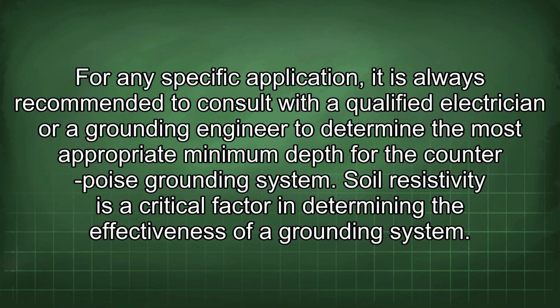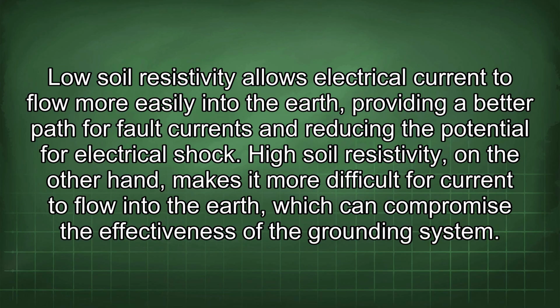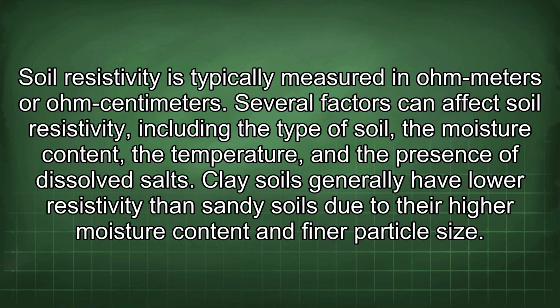Soil resistivity is a critical factor in determining the effectiveness of a grounding system. Low soil resistivity allows electrical current to flow more easily into the earth, providing a better path for fault currents and reducing the potential for electrical shock. High soil resistivity, on the other hand, makes it more difficult for current to flow into the earth, which can compromise the effectiveness of the grounding system. Soil resistivity is typically measured in ohm meters or ohm centimeters.